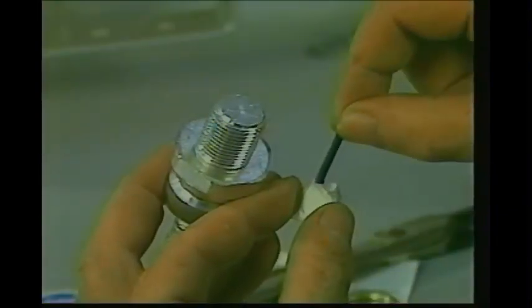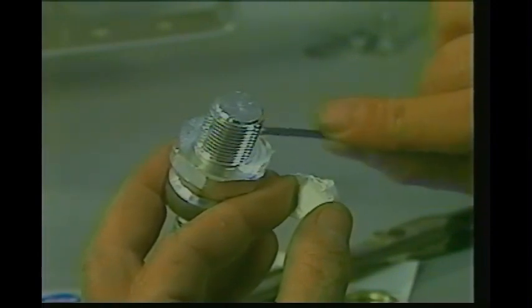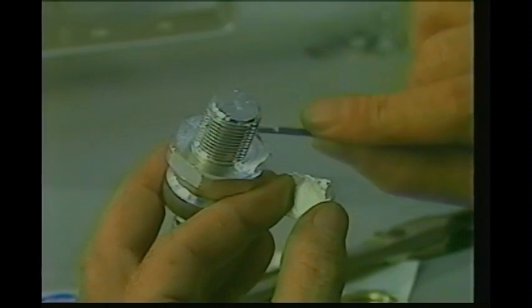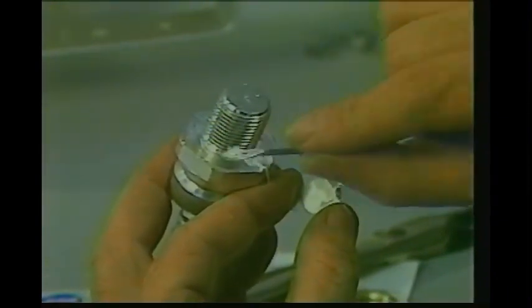The first thing to do when installing a diode is to clean off the heat sink assembly. Remove all the dirt or varnish residue that may be present. Next, cut open the heat sink compound package. Apply the heat sink compound to a match or a toothpick and apply it to the base of the diode. Do not apply any compound to the threads. It is not a lubricant.